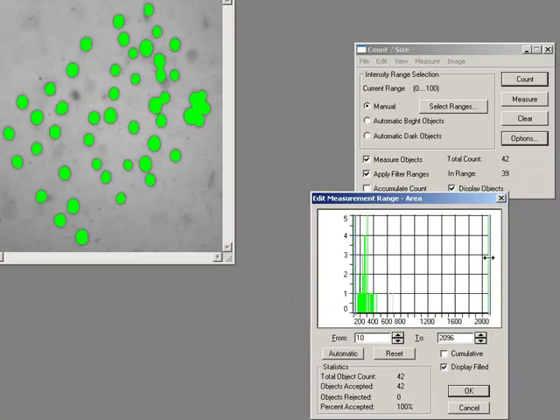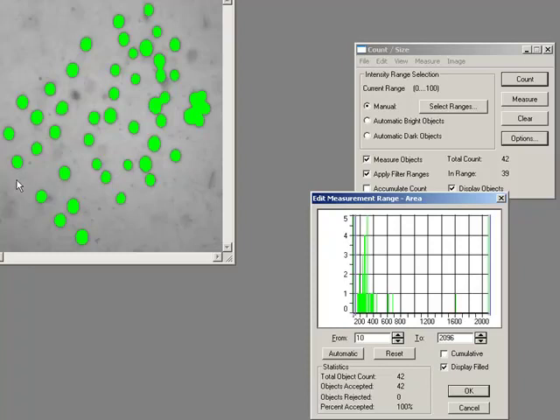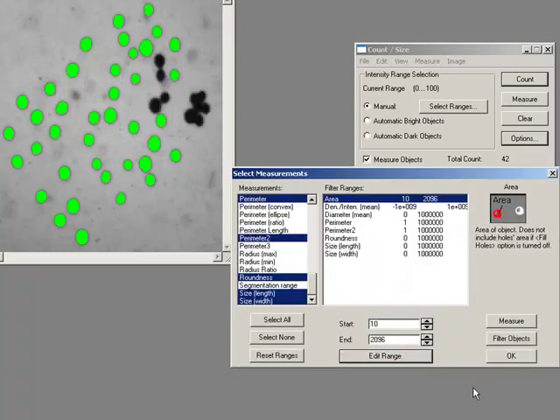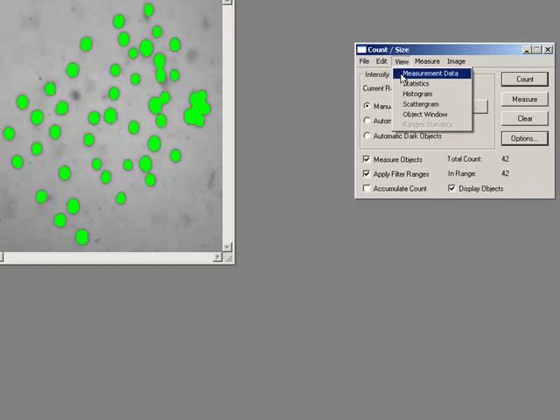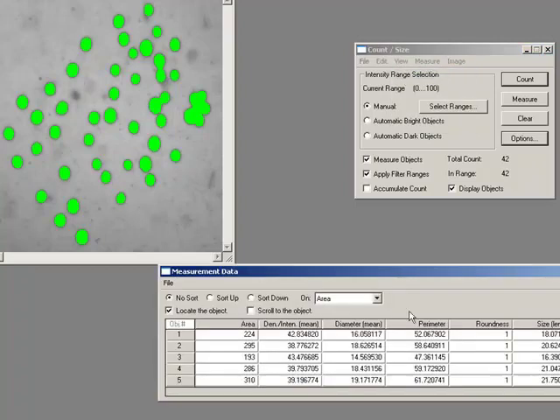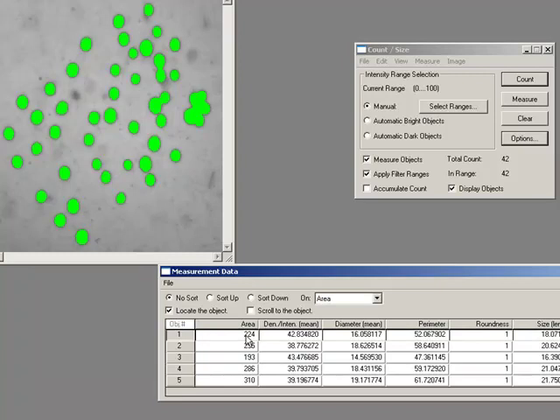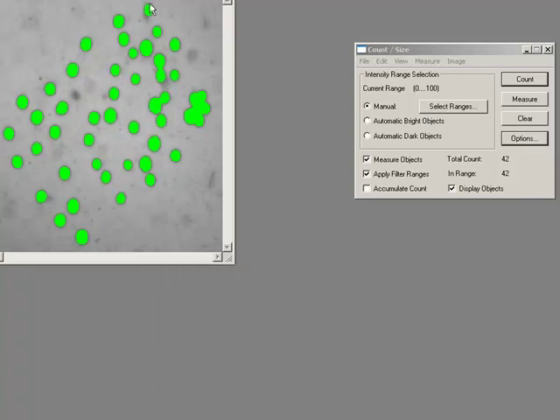It's actually more useful to use when you're looking at small individual objects that are fooling it into thinking it's a cell, normally some bits of noise. We look here, these little dots here in the background. These aren't actually the objects we're looking at, so we want to have them removed from our count. When I go back to the measurement data, we can look at all the values here. The area value of this object here is 224. If I've used a calibration in my work, then all of the values are calibrated, and therefore that's a true micron value or foot value or meter value or whatever we need it to be.